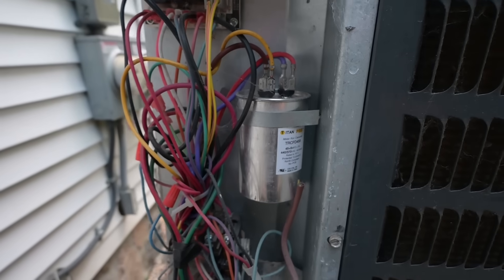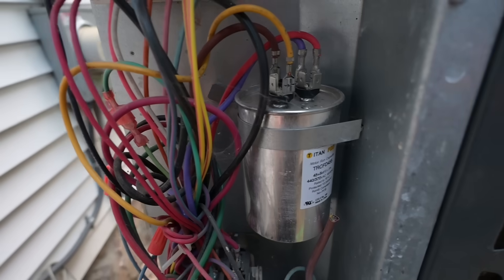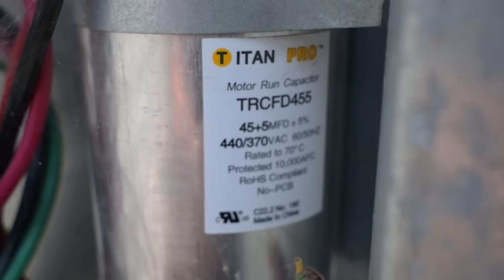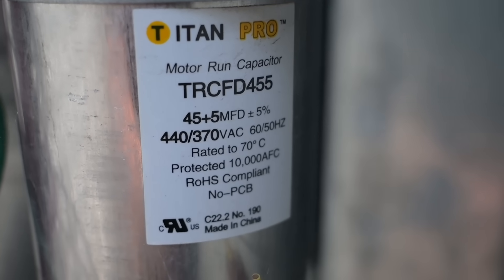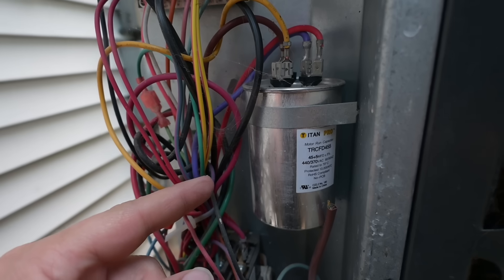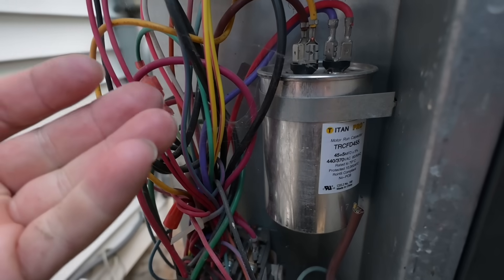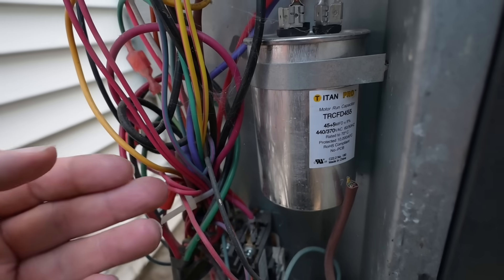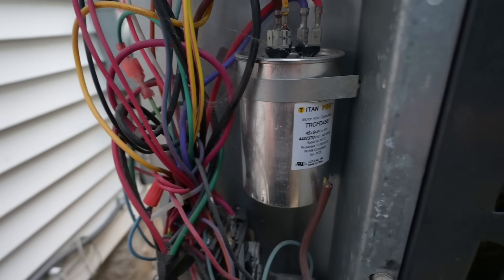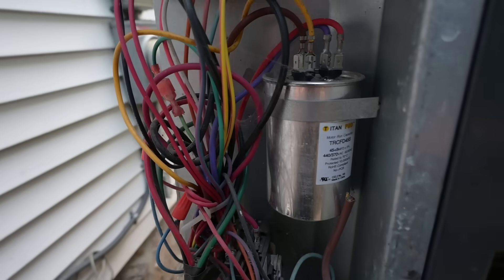Right up there at the top, that's our capacitor. I can't actually see any visual indications of it being bad right now. We're going to remove it from the cabinet. The important information is right there on the side — we have a 45 plus 5 microfarad, plus or minus 5%, and this one's 440 or 370 volts AC. You can replace the capacitor with one that has a higher voltage rating but never lower. Some air conditioners come with 370 volt capacitors, some come with 440. Oftentimes companies will carry just 440, so just go with a 440 if you're not sure.